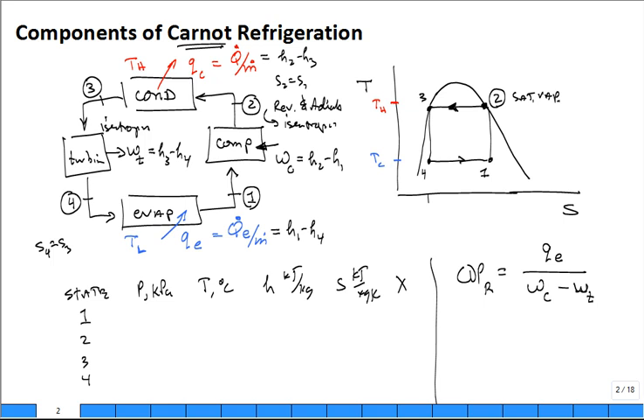Why don't we build Carnot refrigeration systems? Because compressors like to have vapor or superheated vapor. They don't like two-phase, liquid droplets inside the fluid coming into the compressor. Likewise, there isn't a turbine that you feed saturated liquid and expand it. We like to expand vapors or gases in turbines, not liquids. So we modify this system to get what we call a practical vapor compression refrigeration system.